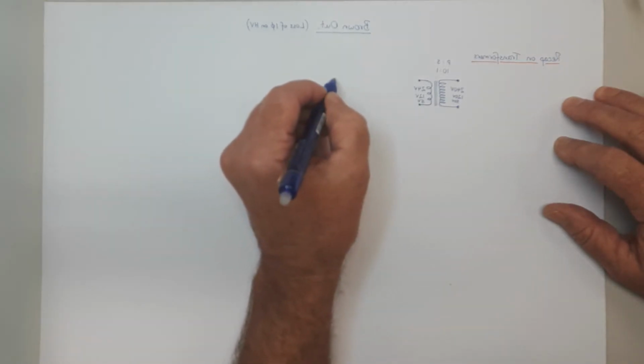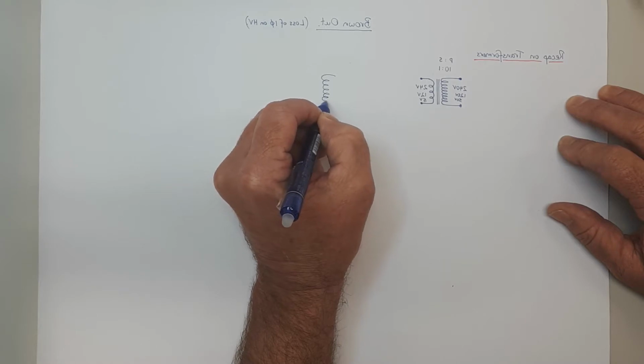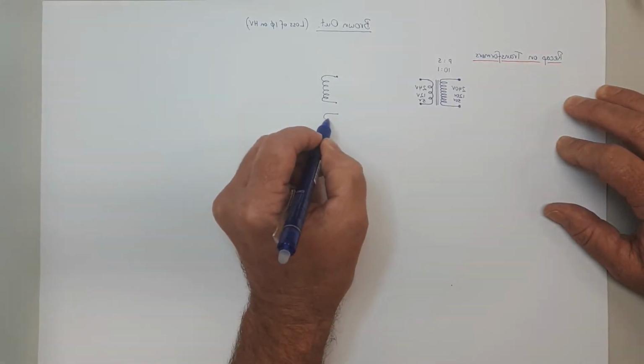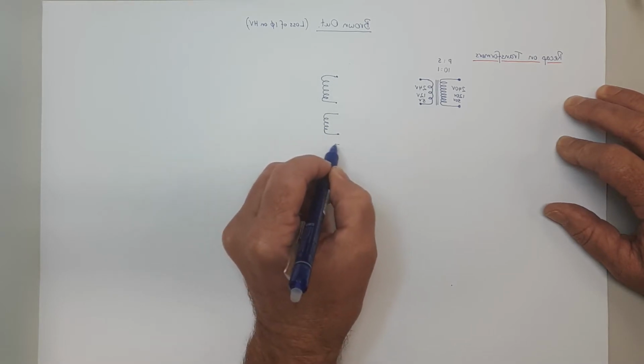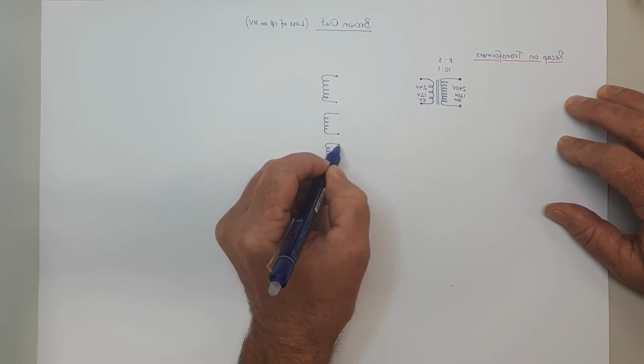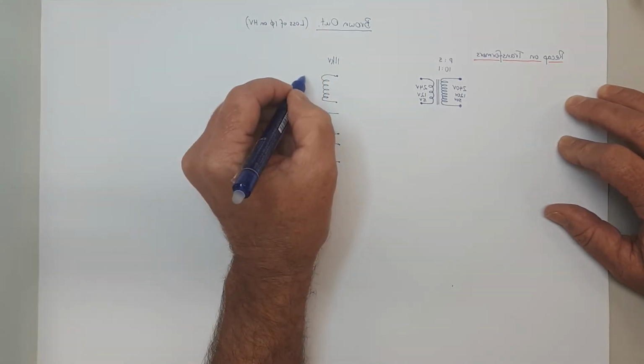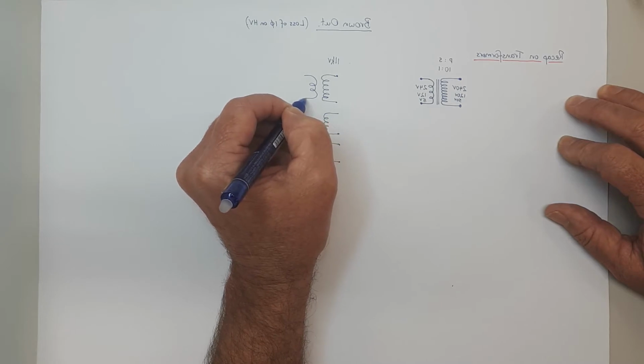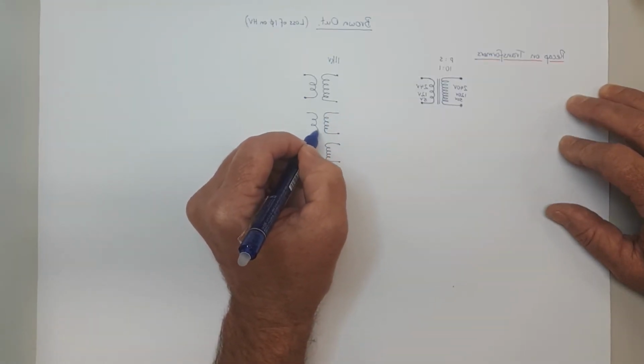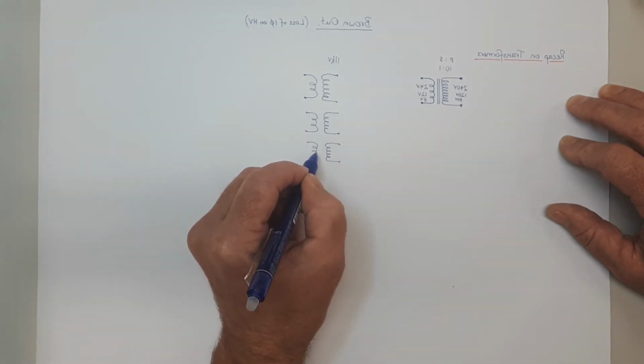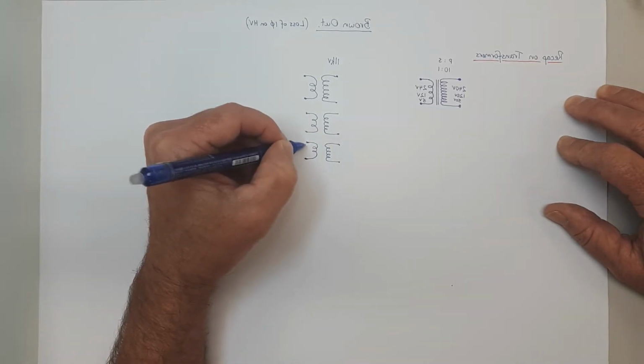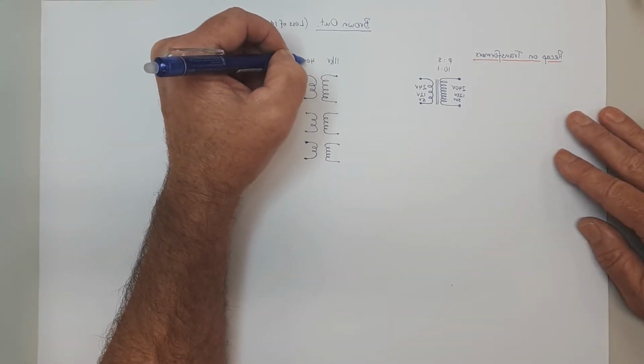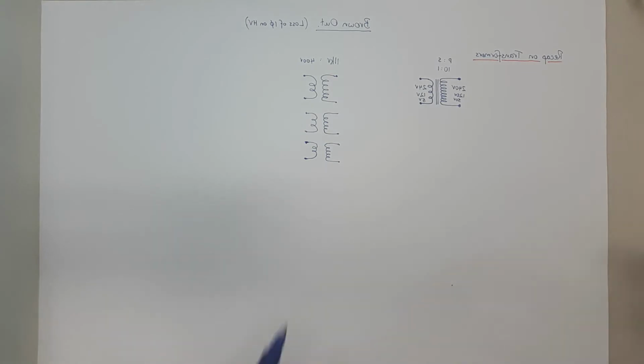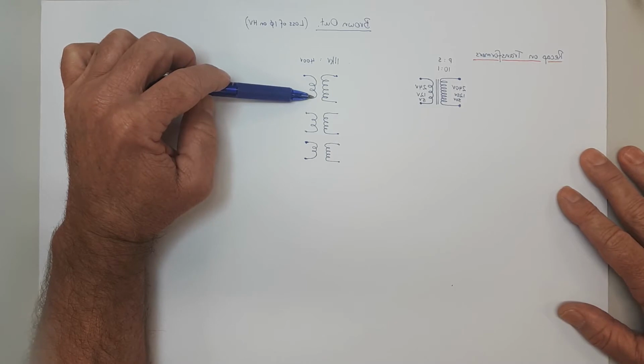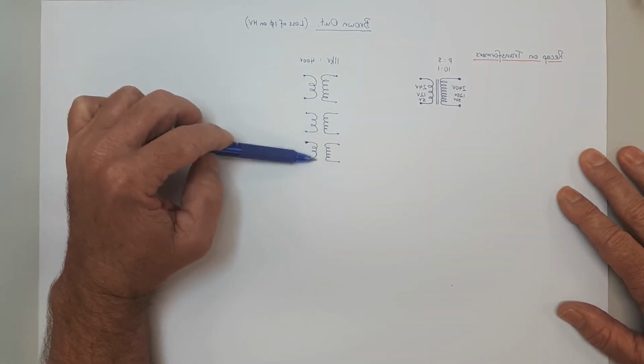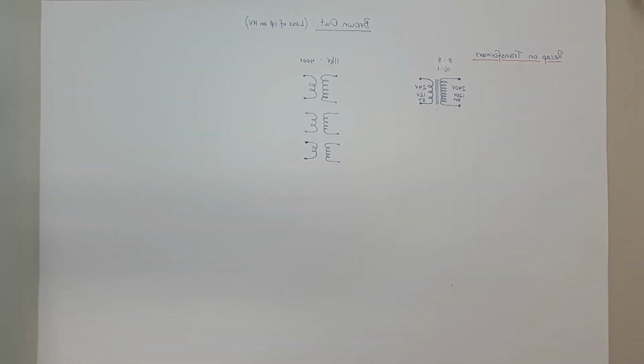So, with that in mind, we can look at a three-phase transformer. A three-phase transformer is the same thing, just 3 times. So if I put in 3 windings here, that's what your typical street transformer is going to look like internally, or as a circuit diagram. This side will be 11 kV, and then this side, as you probably know, will be 400. So it's 11 kV to 400. Some people still like to say 415, but the nominal voltage is 400 on the secondary. What happens is, again, this winding energizes this winding, this one energizes that one, and this one energizes that one, and they operate not completely, but almost independently of each other.